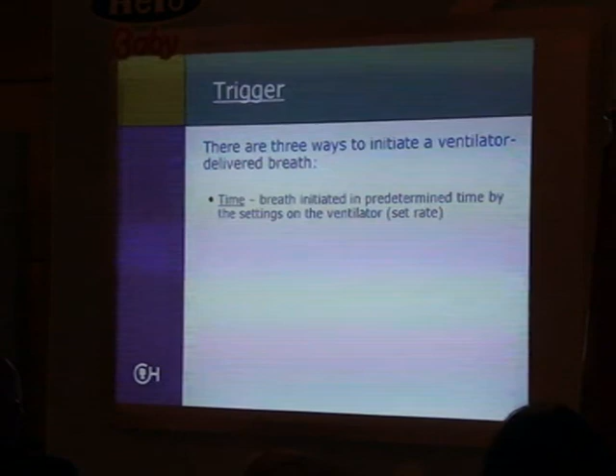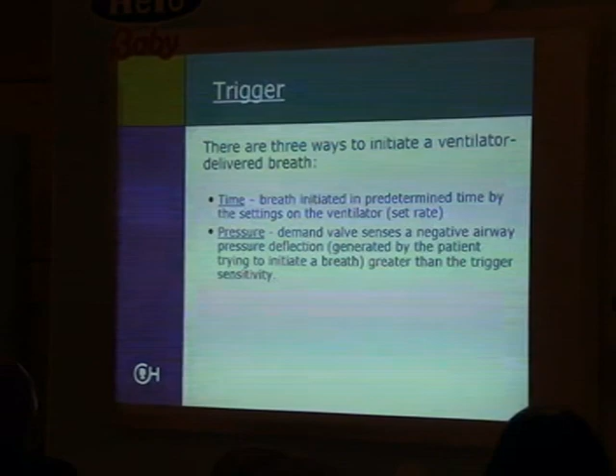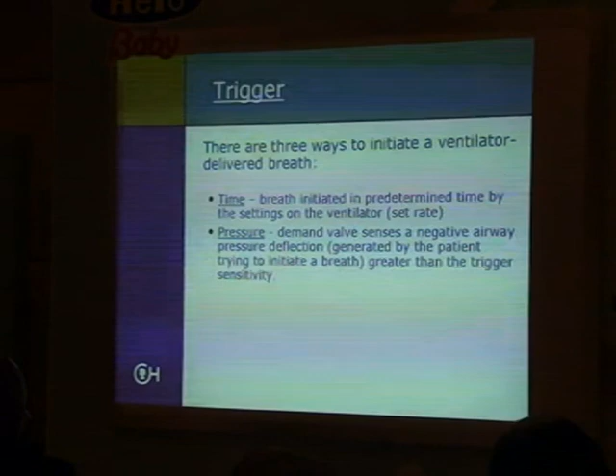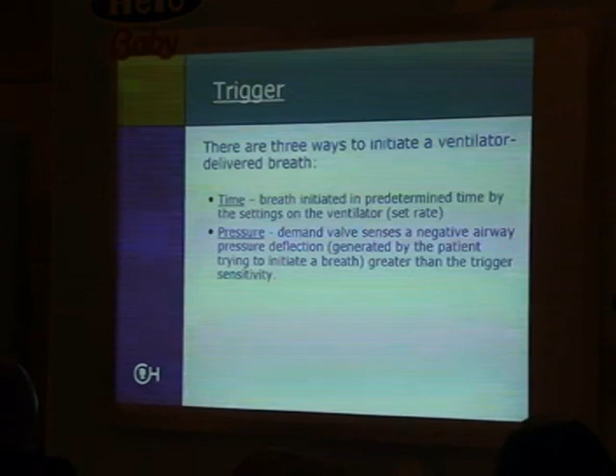As we get into some of our spontaneous modes, there are 2 different ways. One is by pressure, and this is when the demand valve on the ventilator will open up when it reaches a certain amount of negative pressure. So you're taking a deep breath in, or you're starting to take that breath in, and as soon as it sees a certain amount of pressure that is requested, then it gives a breath. And this oftentimes, depending on your mode, is either a full controlled ventilator breath or a spontaneous breath with a little bit less pressure.